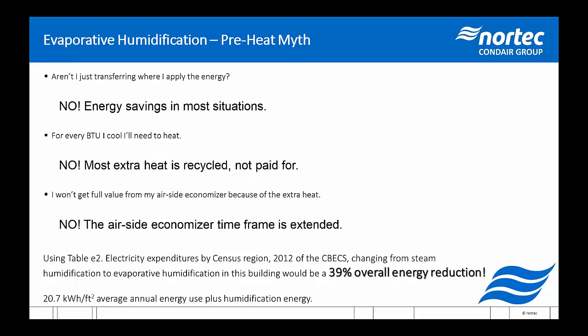In this building, this would have been approximately a 39% overall energy reduction. Heating, cooling, humidification, lighting, plug load, assuming this 20.7 kilowatt hour per foot squared average that I've used from the CBECS census is accurate. The savings that we can apply with this evaporative humidification over electric steam or gas steam is huge. Gas steam is less expensive than electric steam, but the amount of energy applied is the same.